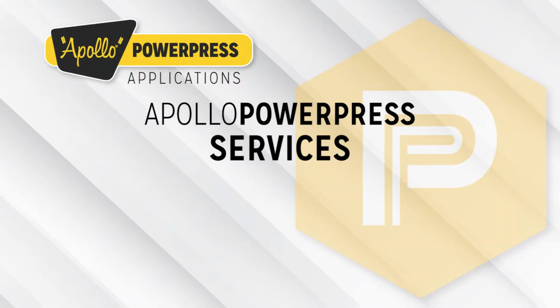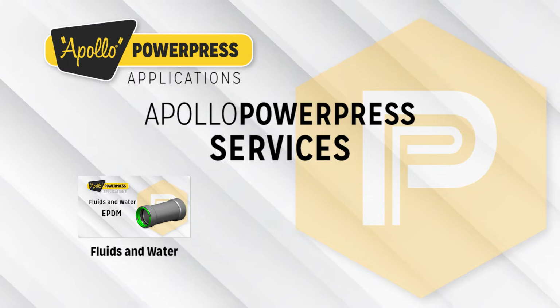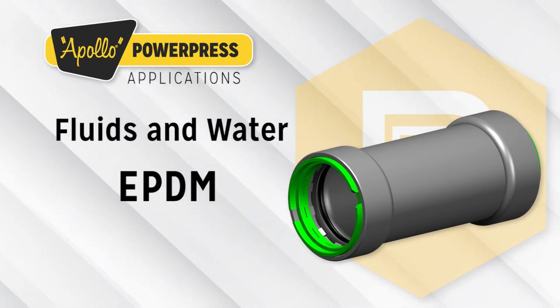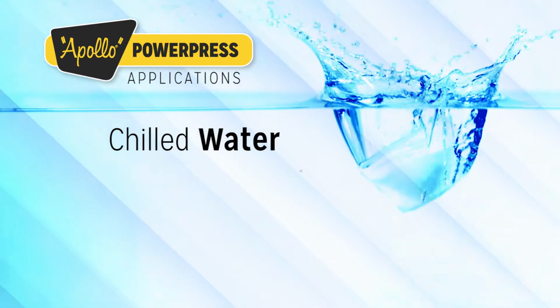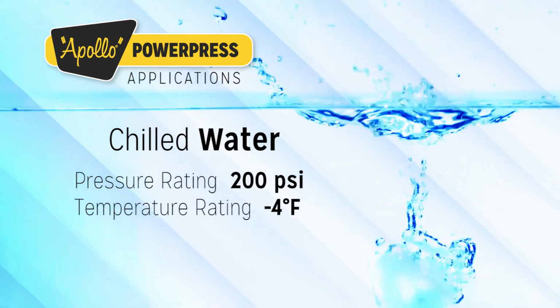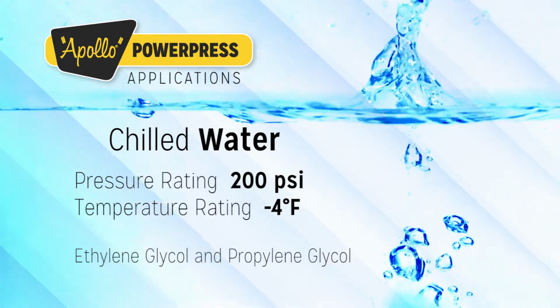Apollo PowerPress has been approved for three main types of services: fluids and water, oil and lubricants, as well as gases. Fluids and water are approved for EPDM sealing elements and include the following subcategories. Chilled water has a pressure and temperature rating up to 200 psi and down to -4 degrees Fahrenheit. Ethylene glycol and propylene glycol are approved.